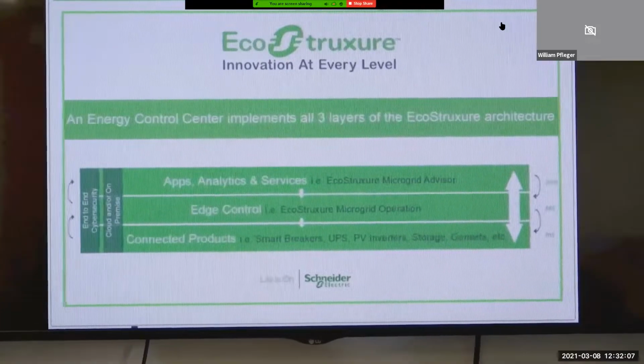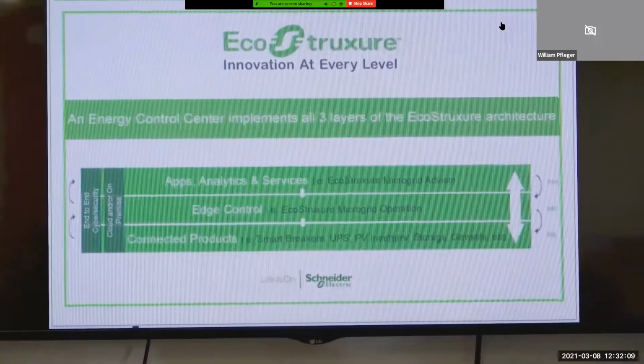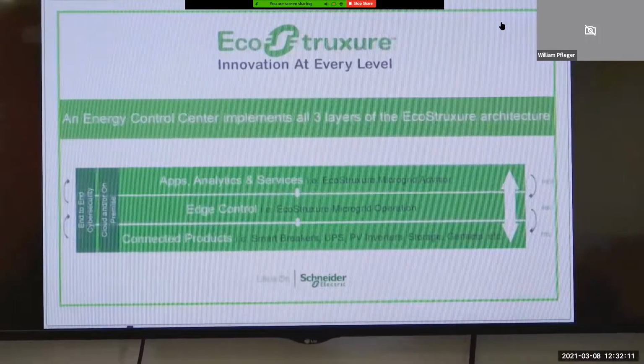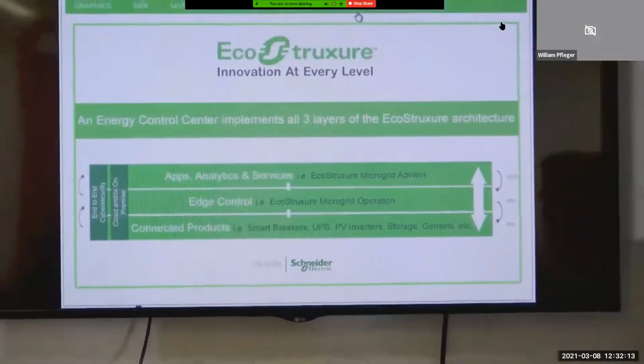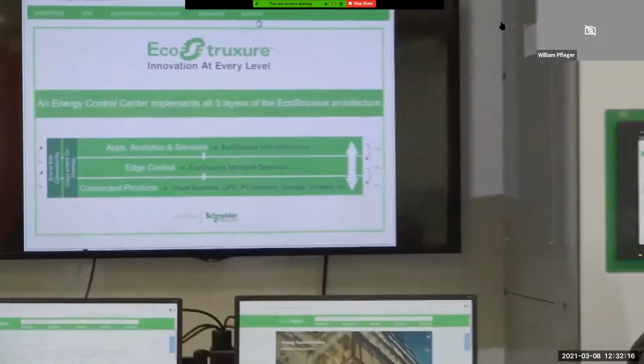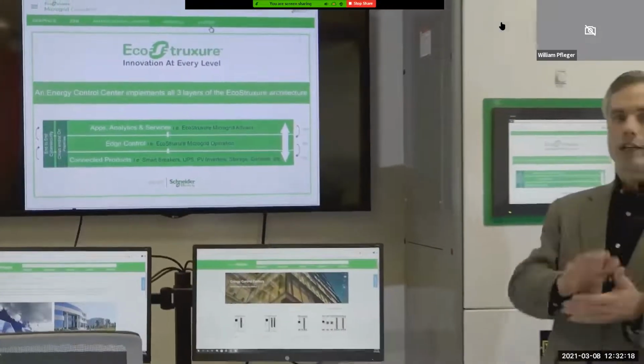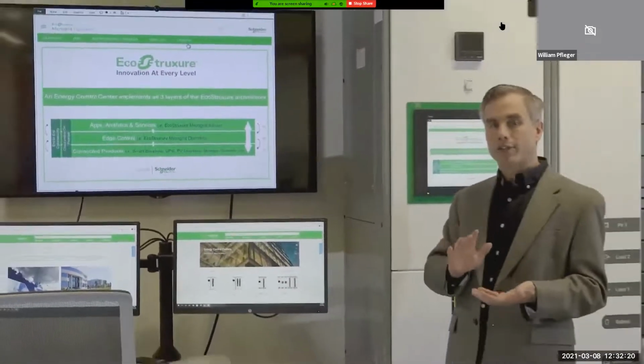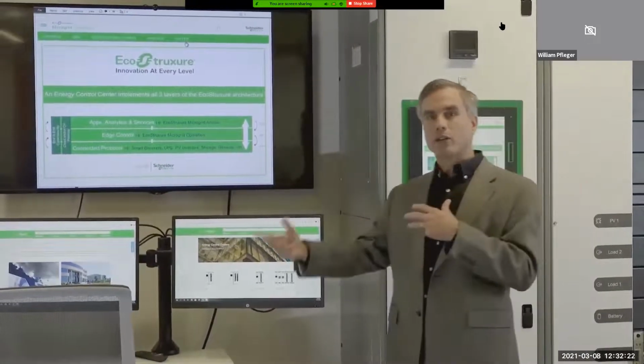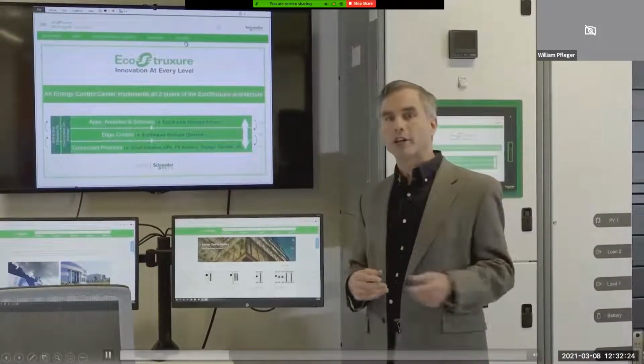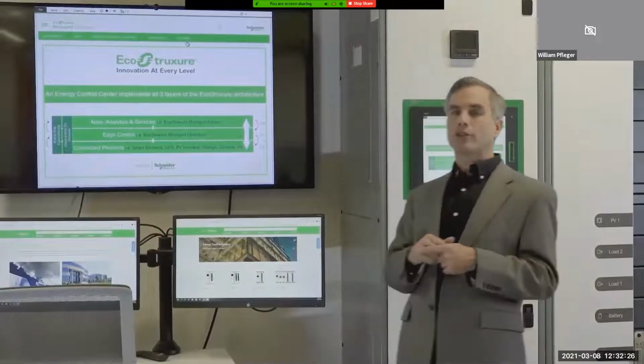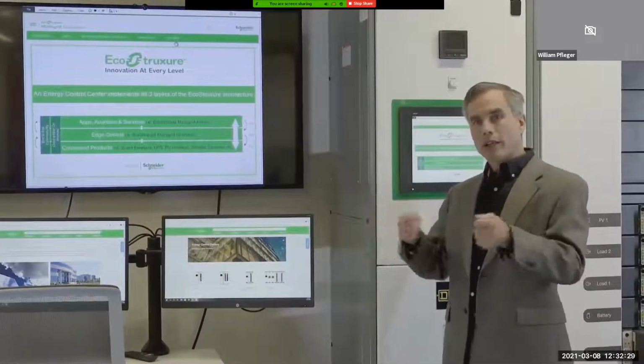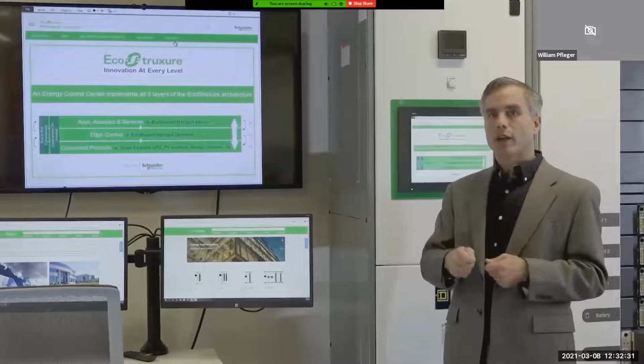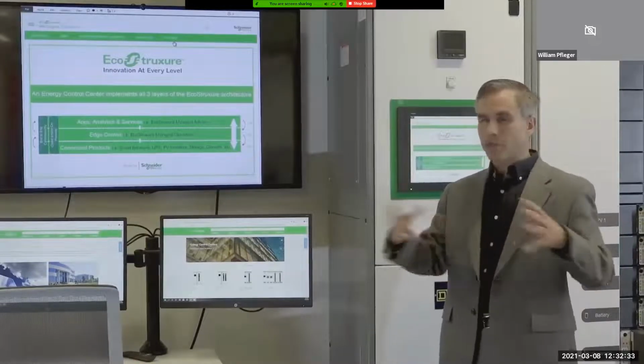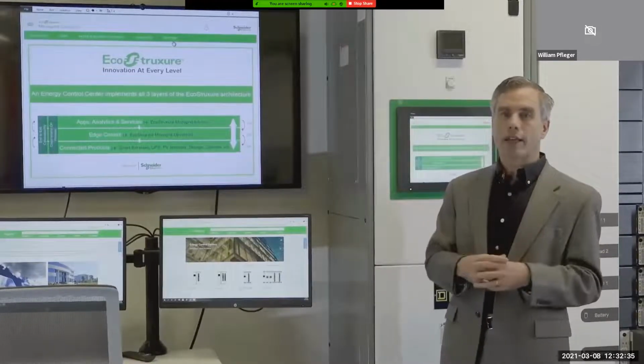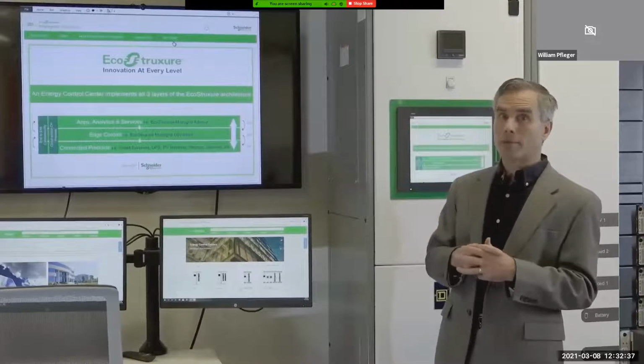For example, if the edge controller found out from one of the breakers that the utility voltage had gone away due to an outage, it could send a command to open the main breaker in the ECC to isolate from that grid that's down. Then it would send a command to start up an anchor resource, like a generator or a lithium-ion battery energy storage system, and sequence in the load breakers quickly. Within seconds, we've got everything back on that the local resources are able to power.